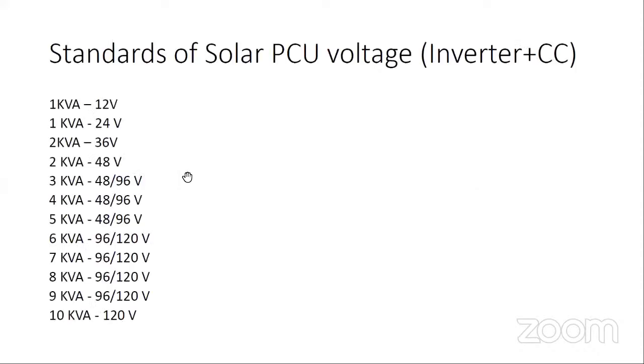Before going into the design, we must know the standards of solar PCUs available. The standard voltage for a 1 kVA PCU is 12 volt or 24 volt. For 2 kVA, it's 36 volt or 48 volt. For 3 kVA, it's 48 or 96 volt. According to requirement, it's not mandatory that it always follows this pattern; it depends on the manufacturer. That's why I suggest taking the data sheet of the product before doing any kind of matching.